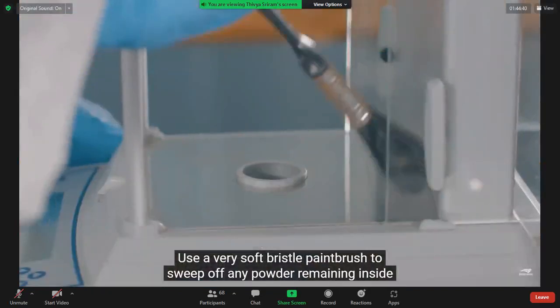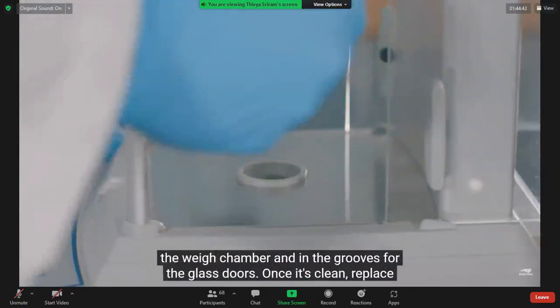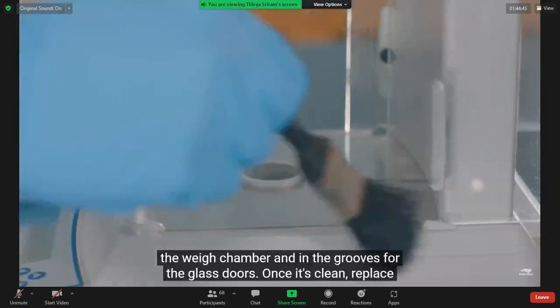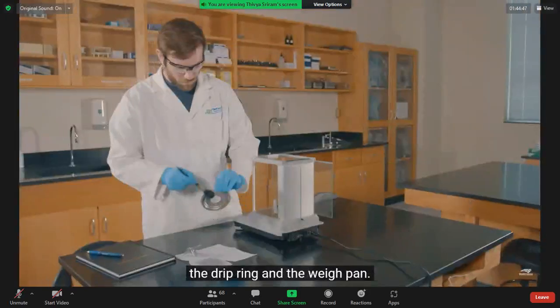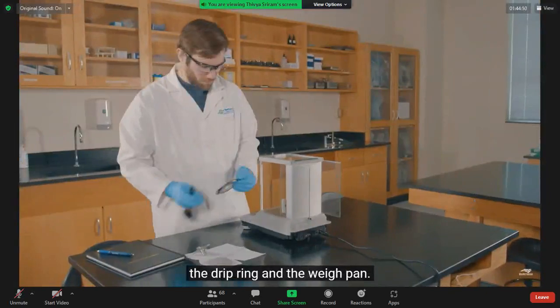Use a very soft bristle paintbrush to sweep off any powder remaining inside the weigh chamber and in the grooves for the glass doors. Once it's clean, replace the drip ring and the weigh pan.